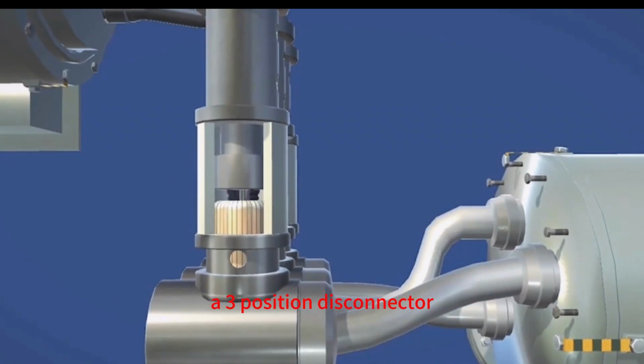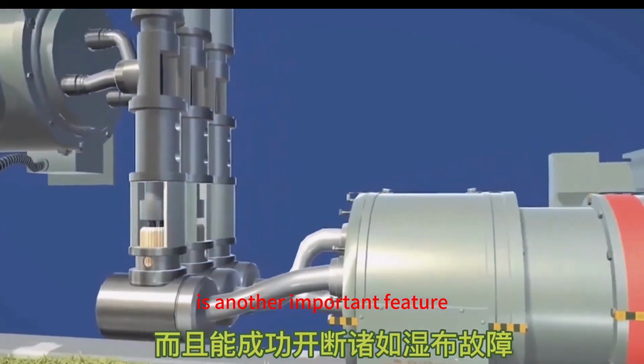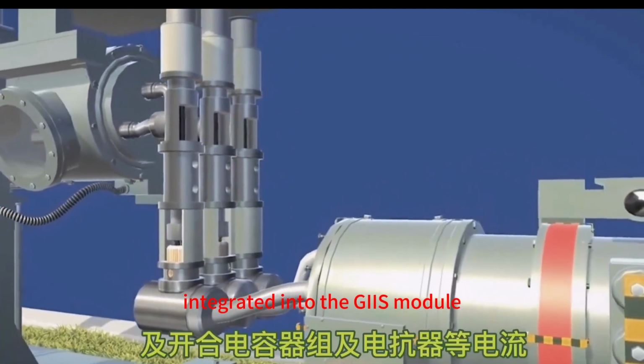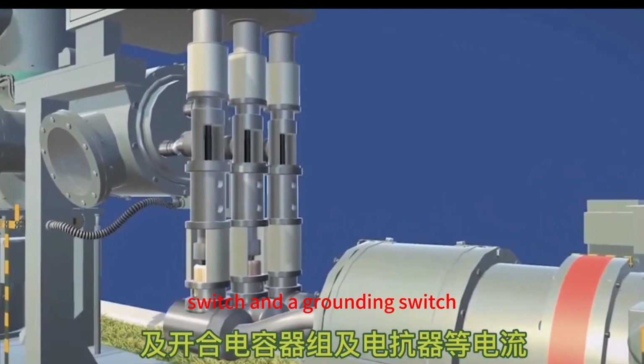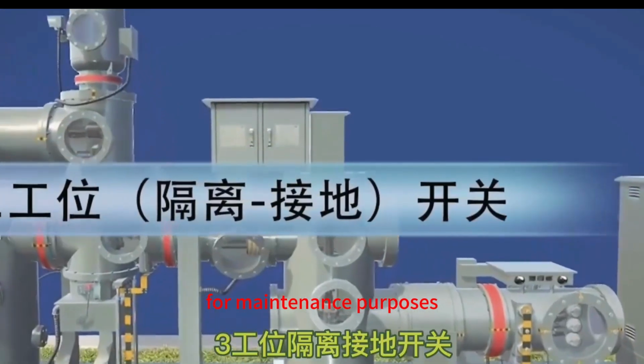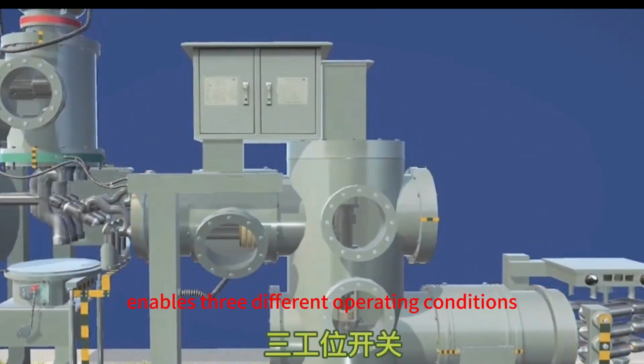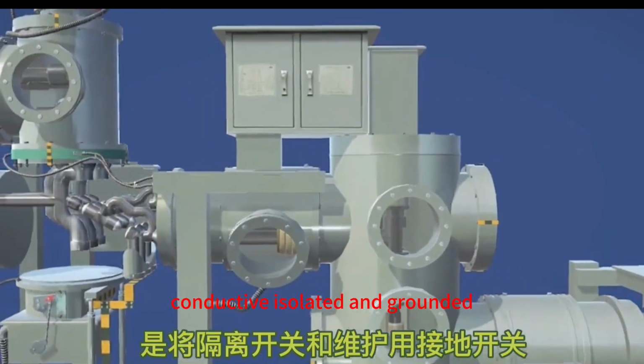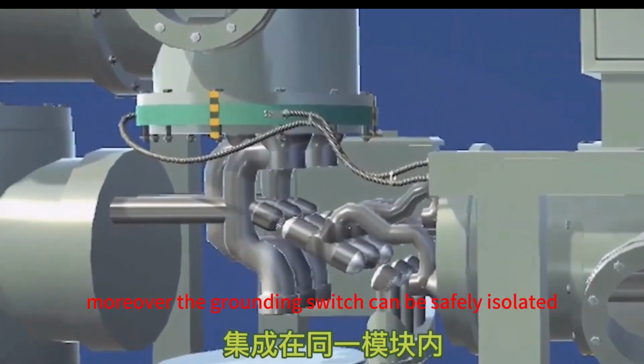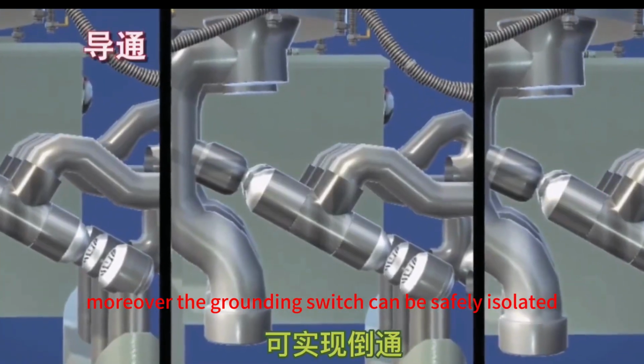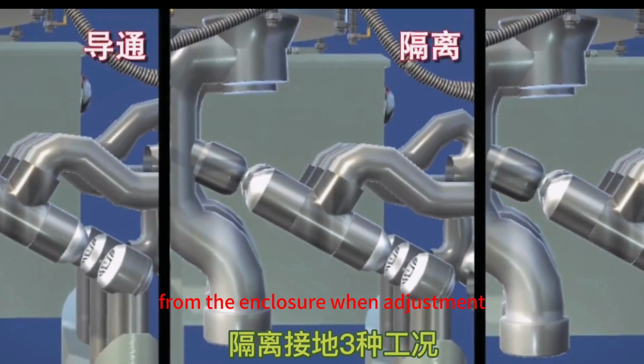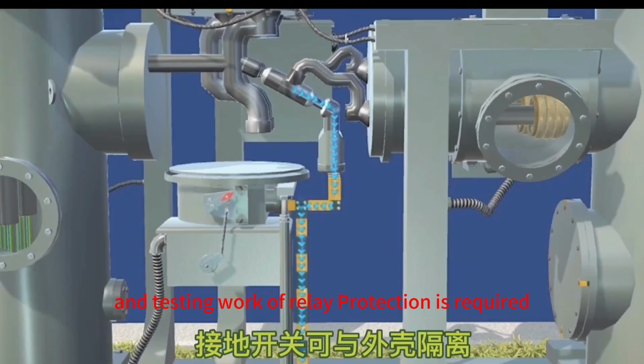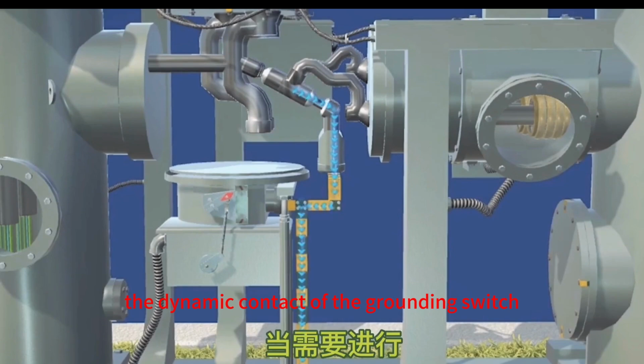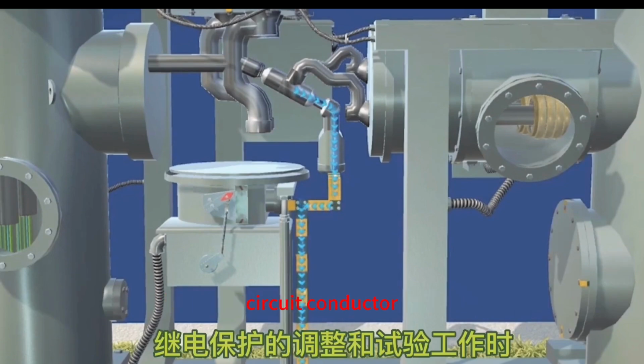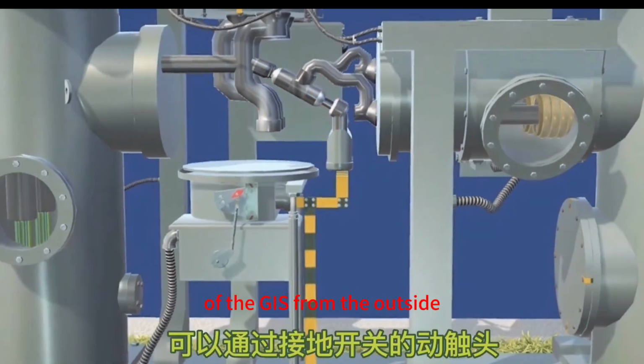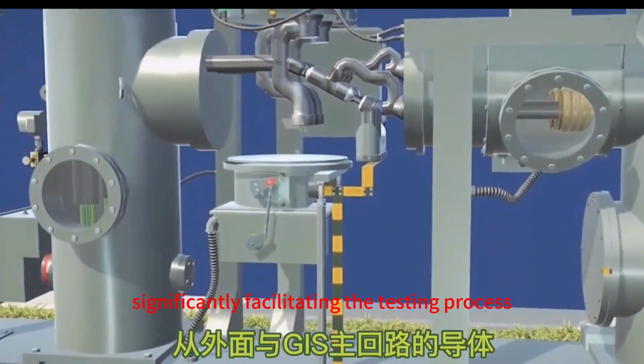A three-position disconnector is another important feature integrated into the GIS module, which combines a disconnect switch and a grounding switch for maintenance purposes. This disconnector enables three different operating conditions: conductive, isolated, and grounded. Moreover, the grounding switch can be safely isolated from the enclosure. When adjustment and testing work of relay protection is required, the dynamic contact of the grounding switch can be electrically connected to the main circuit conductor of the GIS from the outside, significantly facilitating the testing process.